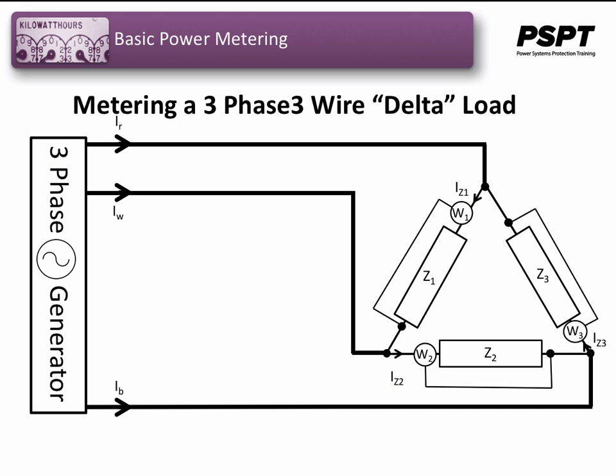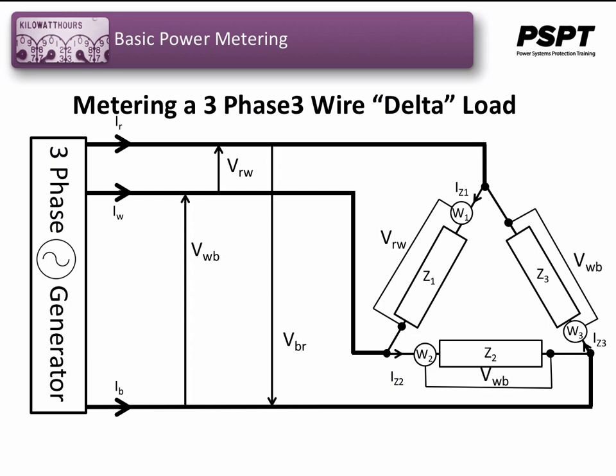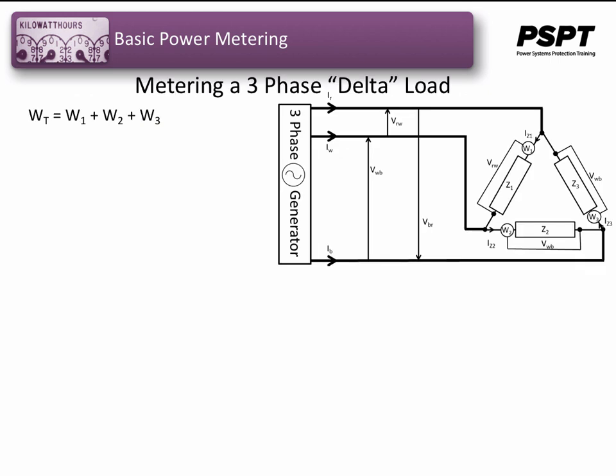Each of the watt meters or elements is connected such that it measures the current through the load and the voltage drop across each load: red to white, white to blue, and blue to red voltage. The total power consumed is the arithmetic sum of the 3 watt meters. So as I said, the total load will be the summation of the individual watt meters, W1, W2, W3, or the individual elements of a 3-element watt meter.